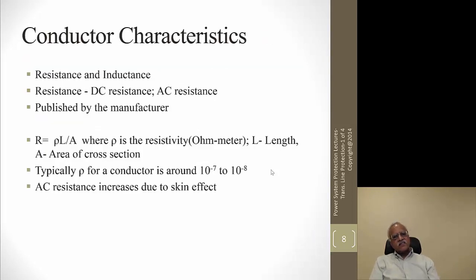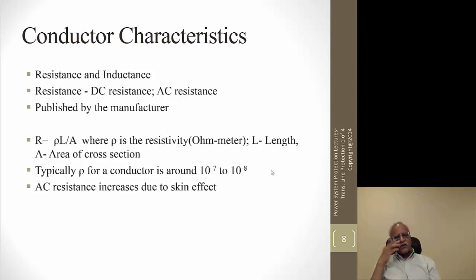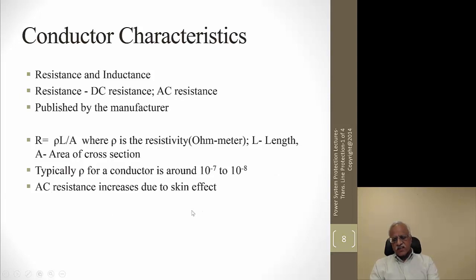Conductor characteristics include resistance and inductance, and we'll discuss capacitance later. DC resistance and AC resistance are both published by manufacturers. The AC resistance increases due to the skin effect, and this is also published in manufacturer catalogs. If you know the conductor type on a transmission tower, you can obtain the resistances from manufacturer catalogs — resistance is resistivity (rho) divided by area.